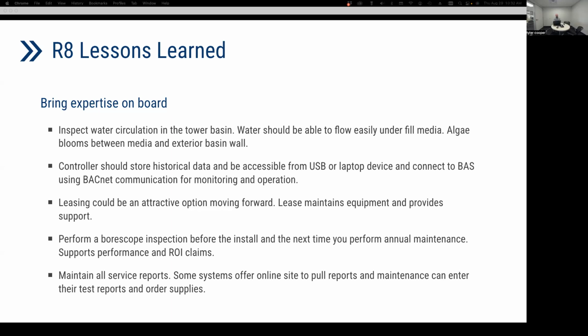If you have the opportunity, having a controller on site that either connects to the BAS and stores that data or is accessible for download gives you real-time analysis of what that system is doing, and it's very helpful for troubleshooting. One of the technologies we did test, we did with a lease. So rather than buying the technology up front, it just came with a monthly service fee with the vendor maintaining that technology and maintaining that alternative water treatment. So that's another option when we're not going with the capital expenditure up front.